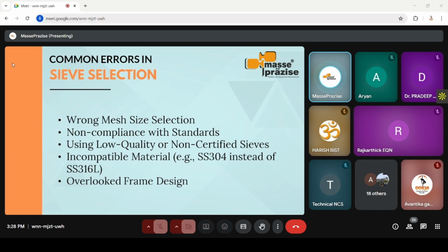Second error that may happen is non-compliance with the standard. Suppose we have selected a sieve that is not as per standard, like ASTM E11, ISO 3310, or USP 786 requirement, that may lead to regulatory risk, and results are not legally defensible in audits. Third point is using low quality or non-certified sieves. Low quality means poor build, like mesh pulled away from the frame, or corrosion-prone material, or a non-certified sieve with no traceability. These things may lead to contamination, inaccurate particle sizing, and failure in quality audits.